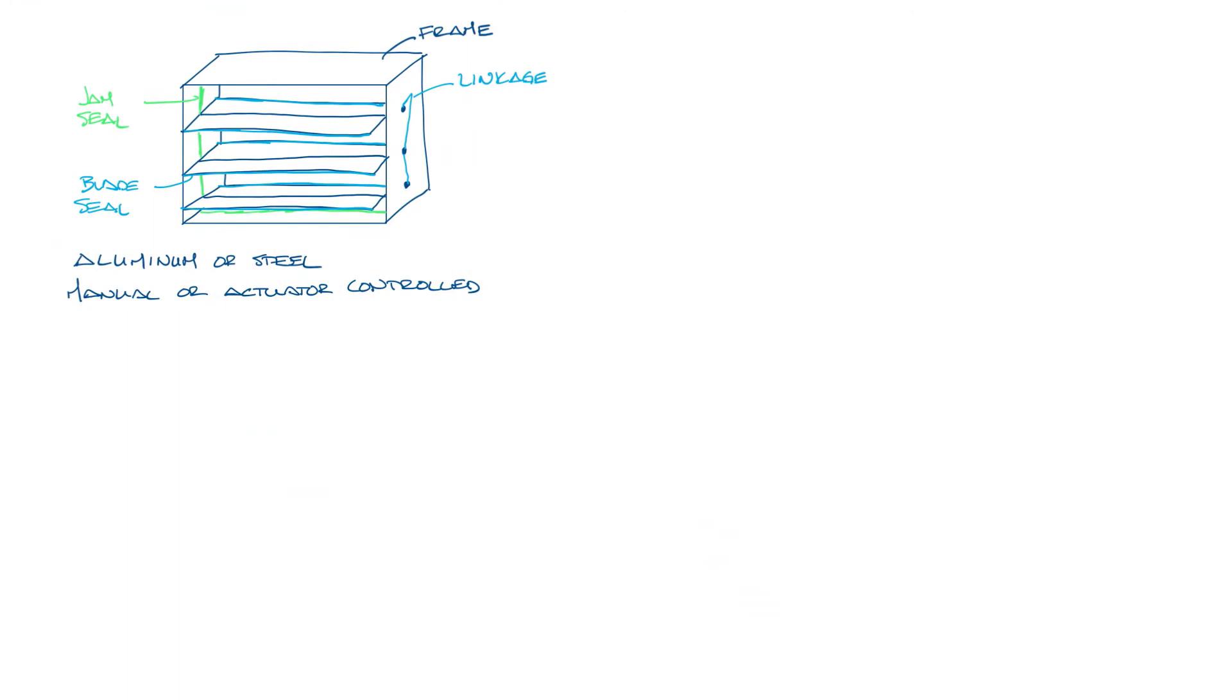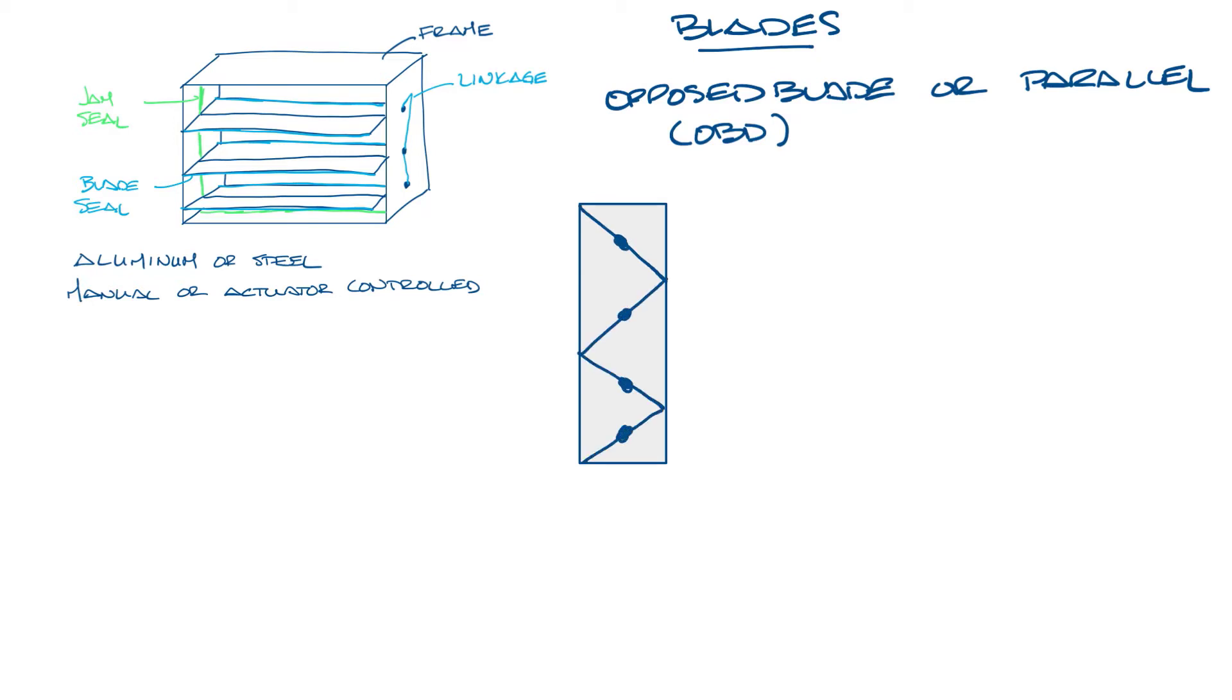Let's move this out of the way. Dampers can be opposed blade or parallel blade design. Opposed blade dampers, also known as OBDs, have blades that open and close in opposition to each other like this. The benefit to this is that the airflow leaves the damper in pretty much a straight and uniform distribution. So if you need uniform airflow like maybe over an electric heater, OBDs are a good choice. OBDs can also be a little quieter in partial open situations.